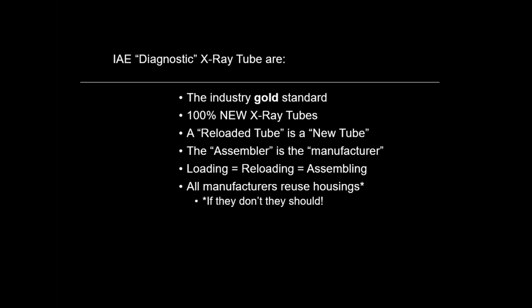So, a couple things about diagnostic tubes. This is not a promotion. I should have taken this IAE out. IAE is a manufacturer. But in general, these diagnostic X-ray tubes are the industry gold standard for those systems. As long as it has a new insert, even if it's a used housing and has used components, it's considered a new X-ray tube. There's no difference between a new X-ray tube that you would buy from your OEM and an X-ray tube that's reloaded, as long as it's been loaded with a new insert and the adequate components.